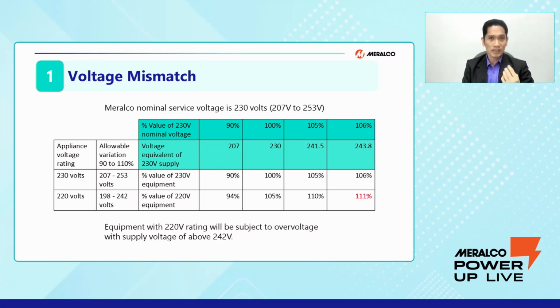At 90% of the nominal voltage of 230 volts, that is 207 volts, the 230 volt equipment is also at 90%, but for 220 volt rated equipment, it is already 94%. At 100% of the nominal voltage, that is 230 volts, for 220 volt rated equipment it is already 105%. And at 105% of the nominal supply voltage, that is 241.5 volts, for 220 volt equipment it is already 110%. So any voltage above 242 volts, or above 105% of the 230 volts nominal, puts our 220 volt equipment in an overvoltage condition. It is very destructive and might damage our equipment, not abruptly, but in the long run. It might be a surprise to us.